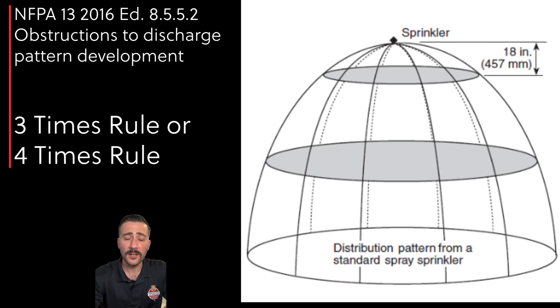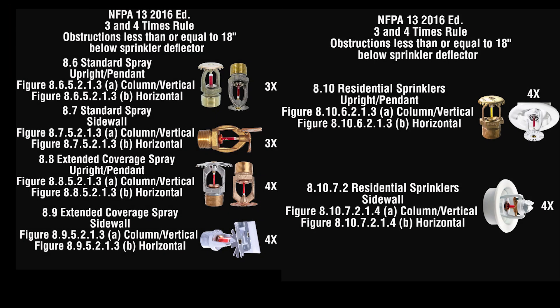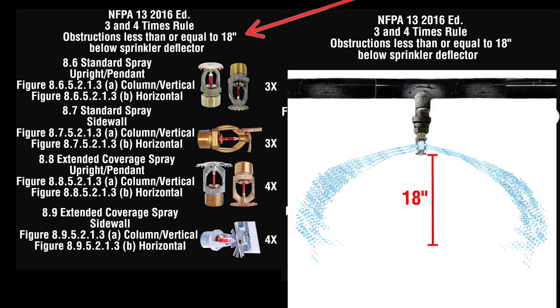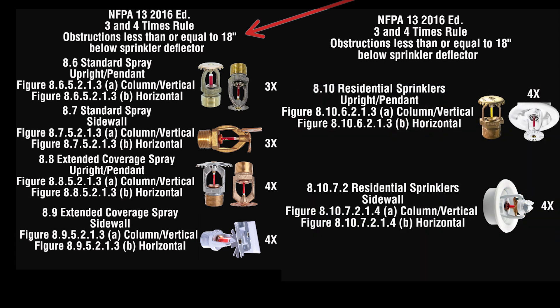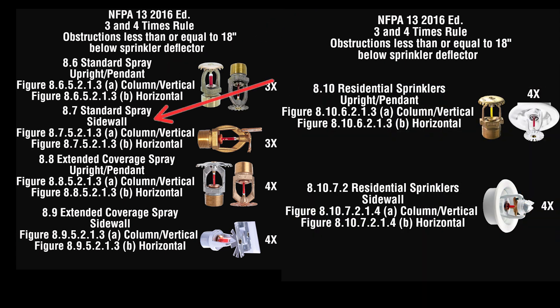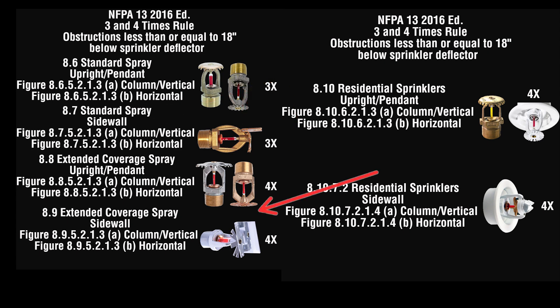This is where you will learn the three and the four times rule. Here you can see all the different style heads listed in NFPA 13 that utilize the three and the four times rule for obstructions that are less than or equal to 18 inches below the sprinkler deflector. The standard spray upright, pendant, and standard spray sidewall utilize the three times rule. The extended coverage upright, pendant, sidewall, and the residential upright, pendant, sidewall will utilize the four times rule.